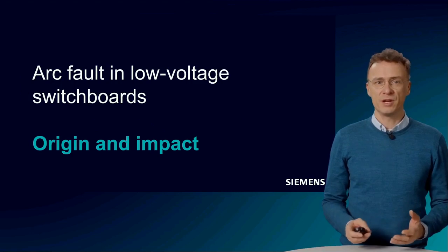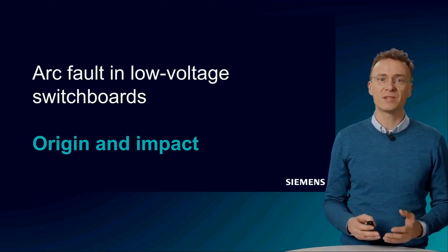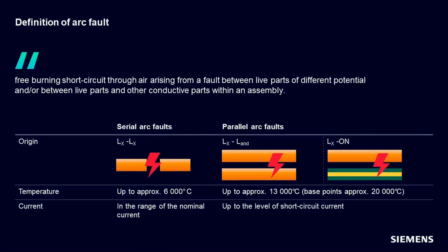Before we go deeper, we should first look at what an arc fault is and what can lead to this worst-case scenario. According to the definition in the standard, an arc fault is a short circuit burning freely in air that can occur as a result of a fault between active parts of different potentials and/or between active parts and other conductive parts within a switchgear assembly. This ionizes the air and makes it conductive, allowing current to flow more or less unhindered in the resulting plasma.